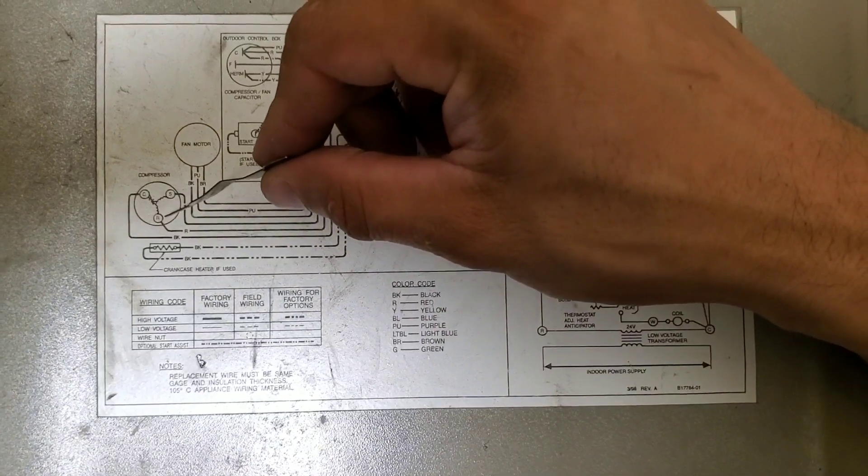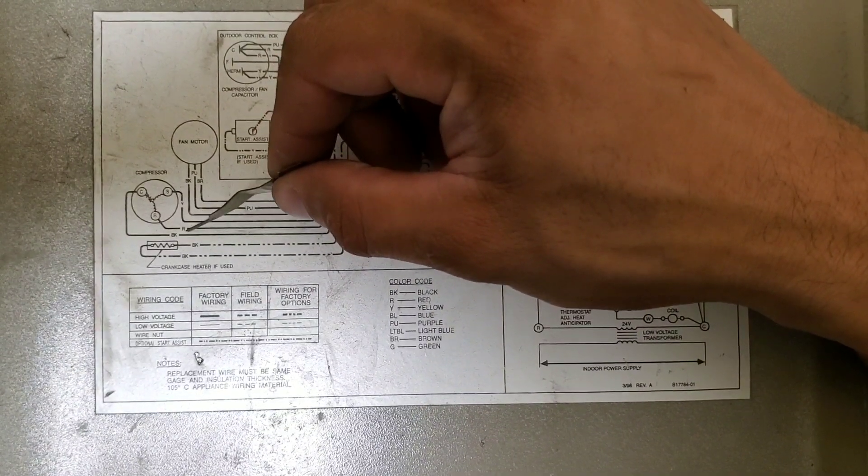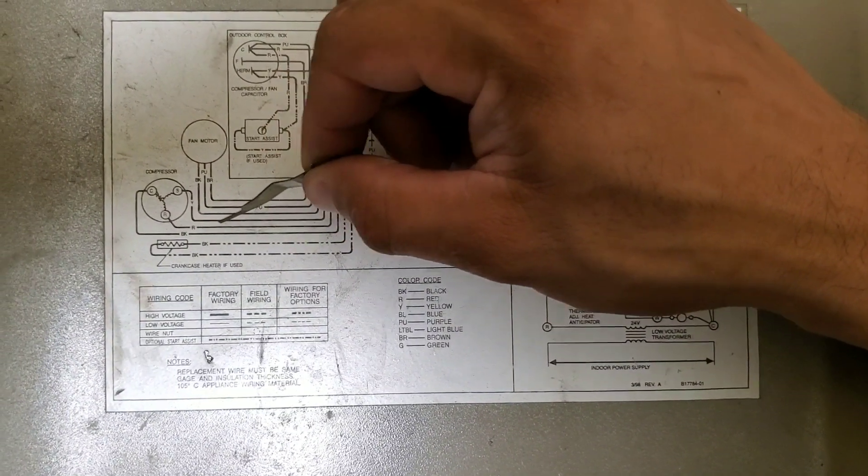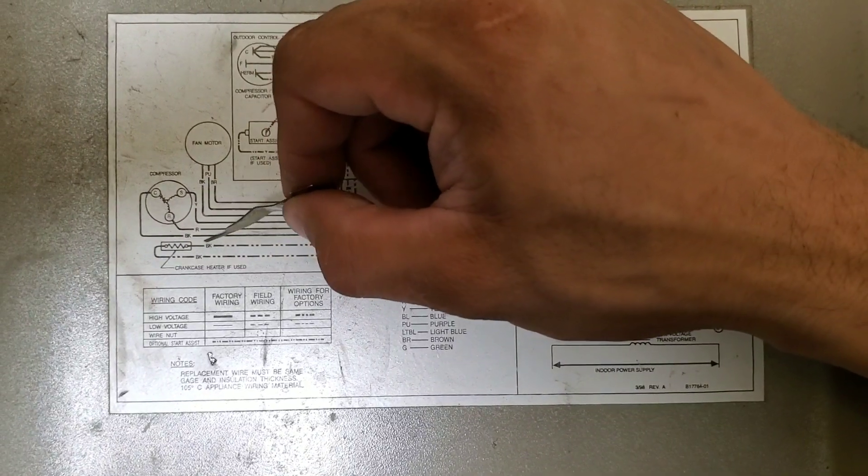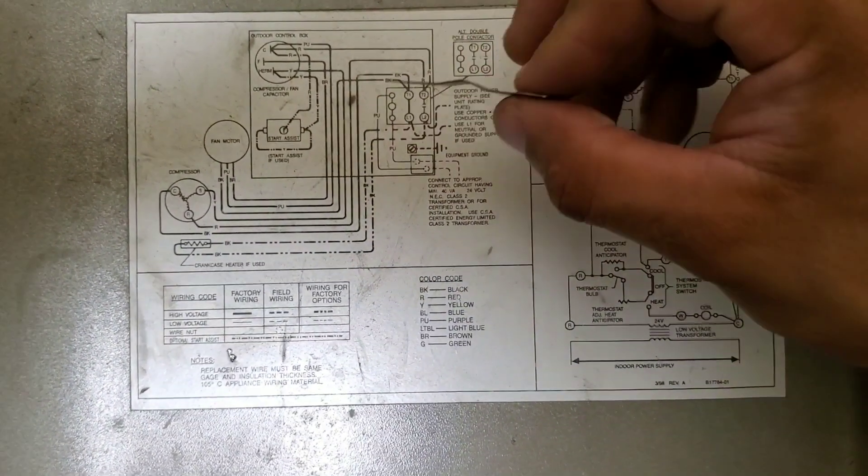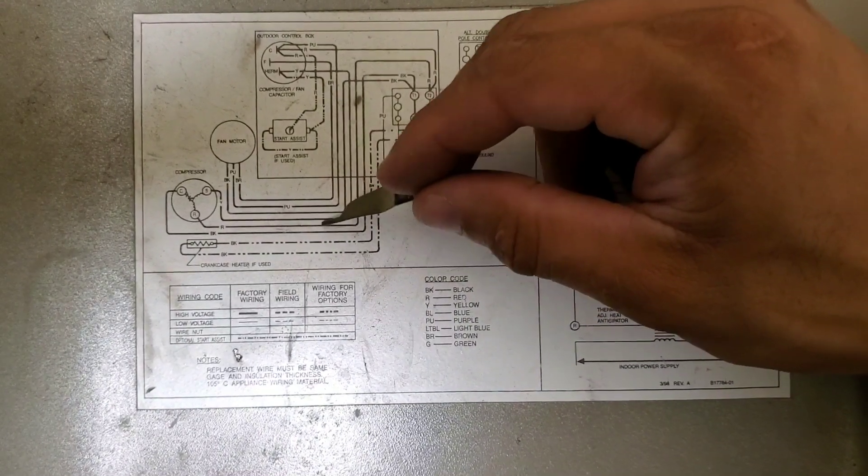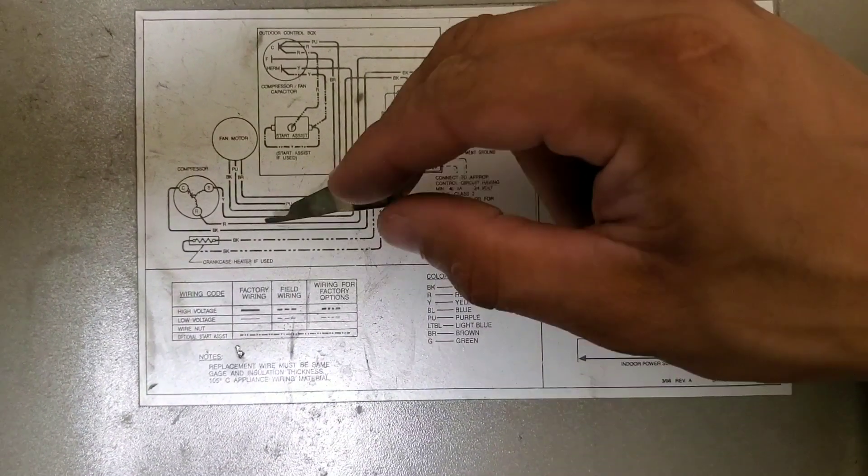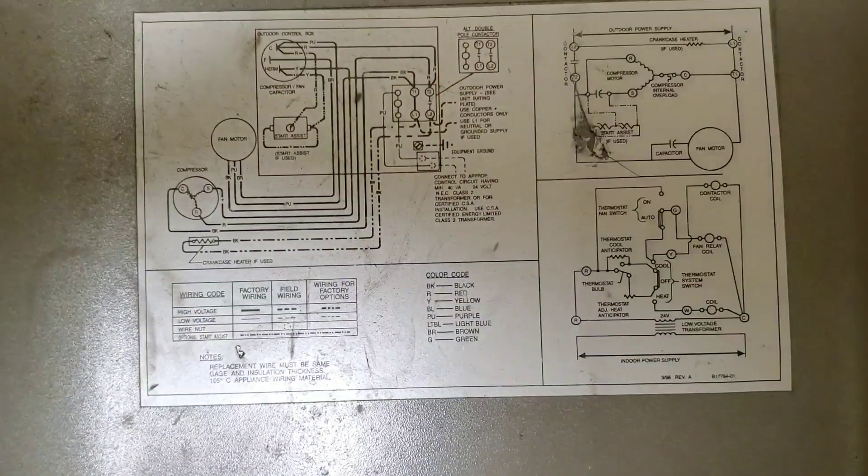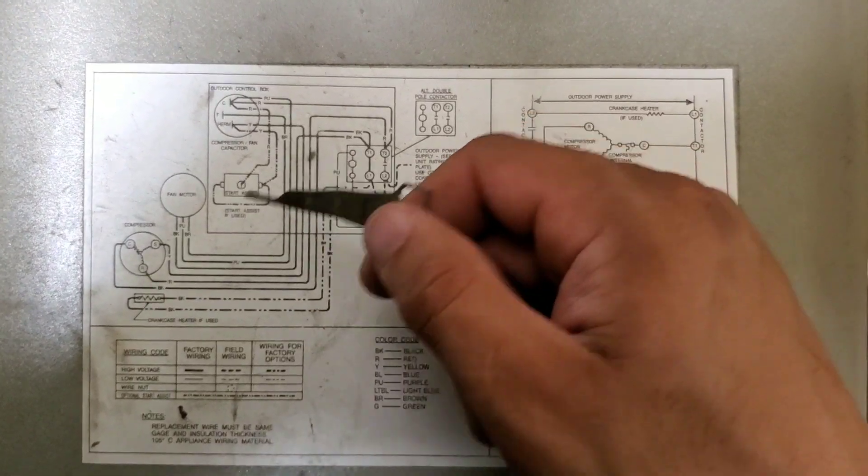You'll see here off the start from the compressor it's labeled Y, the run is R which is red, and the common is black. But a lot of times, especially when you're putting in a new compressor, the harness on the wires that feed to the new compressor, the colors are different.